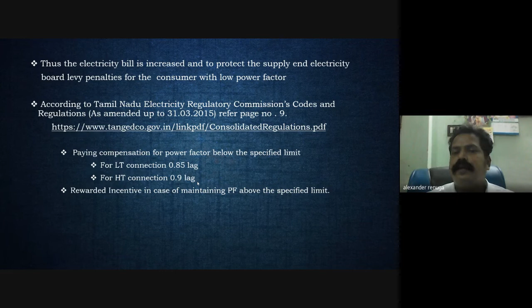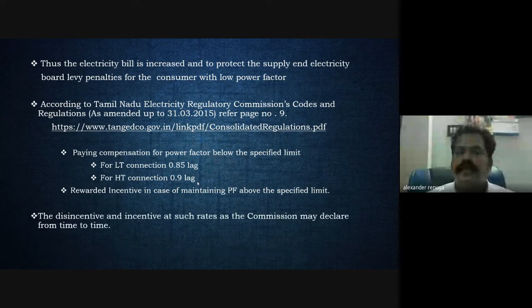Also, an incentive is rewarded for maintaining the power factor above the specified limits. Incentives and disincentives are at such rates as the commission may declare from time to time; they may vary. Power factor correction technique: in industries they use more motors, and a motor is nothing but an inductive load. If you increase the inductive loads, the power factor will go down. To compensate for that, we need to install power factor correction techniques. The power factor correction technique is nothing but simple capacitor banks.